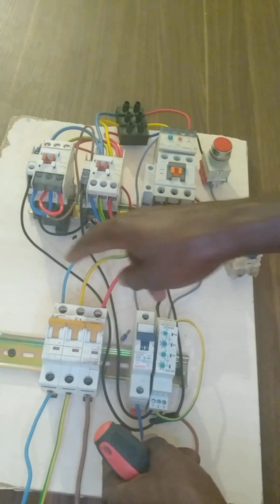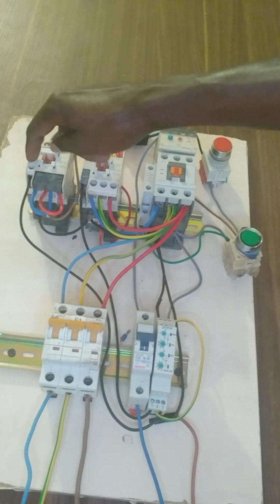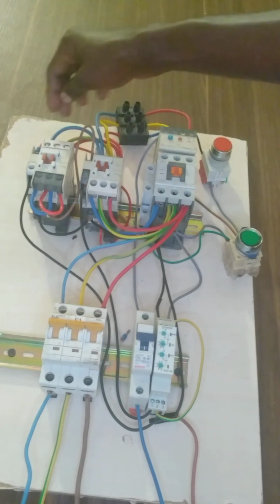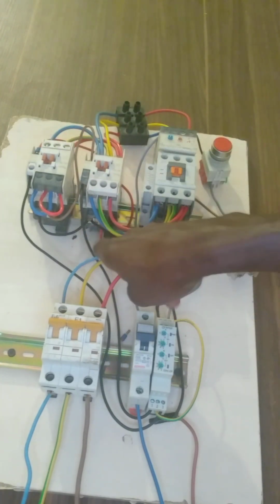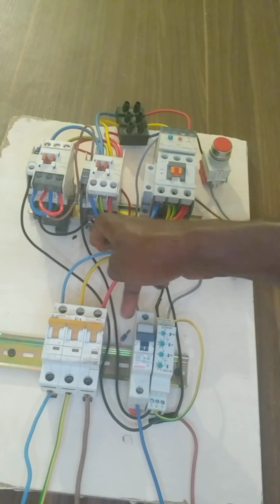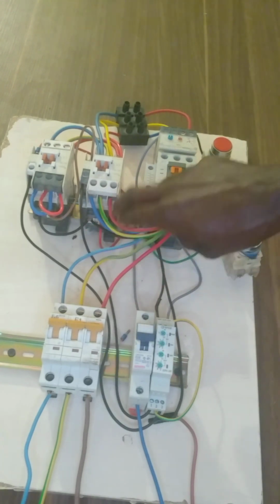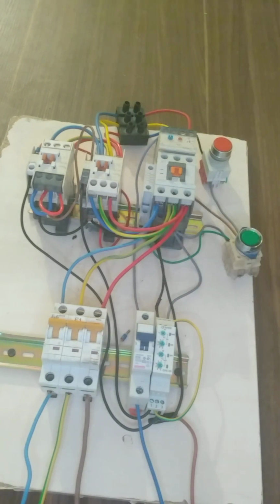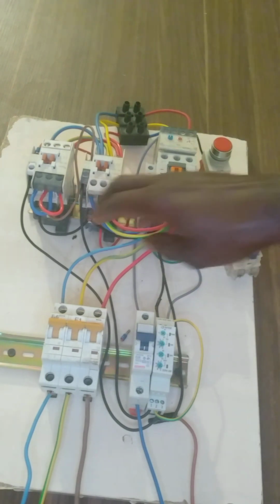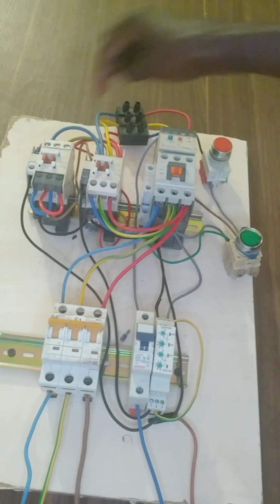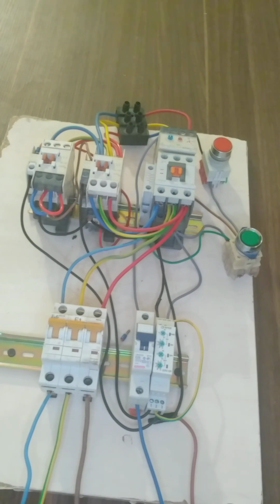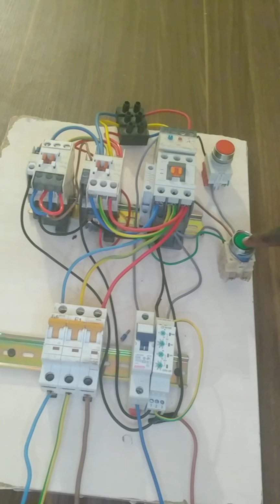Number 3, I go to the normally closed contact of the star contactor. Then I return back to the coil of the delta contactor. This is the electrical interlock, and it protects our circuit more and more. Now I start. So as you see, main and star are starting. After that, it changes to delta.